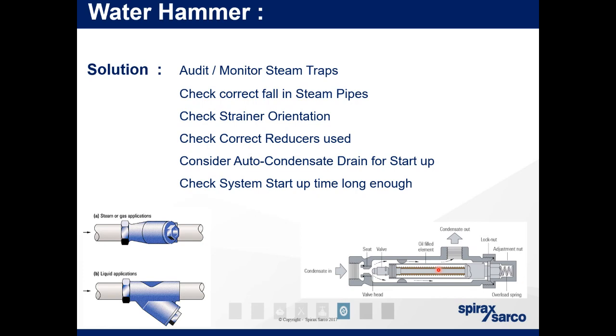We, as a global company, would recommend SG iron used as a minimum grade instead of cast iron. The reason being, as we touched upon before, with microfractures, if you have a steam trap which is seeing water hammer, it's being hammered effectively, hence the name. The material is being hit hard. It can introduce microfractures, so fractures you cannot see. And then at one point it will give way, it will split.